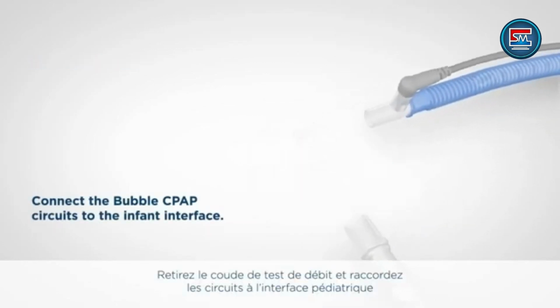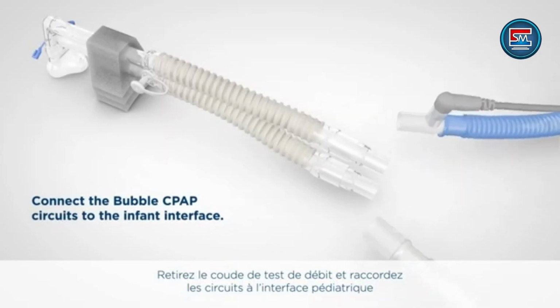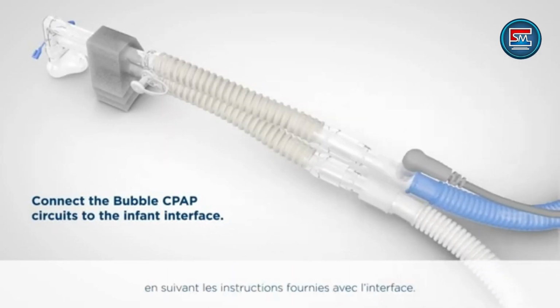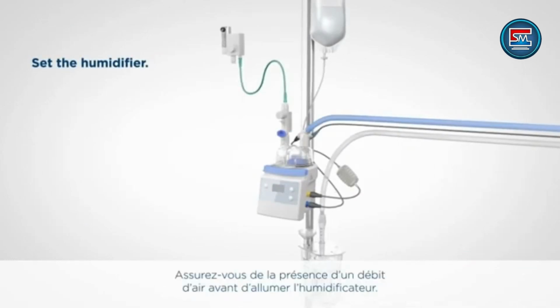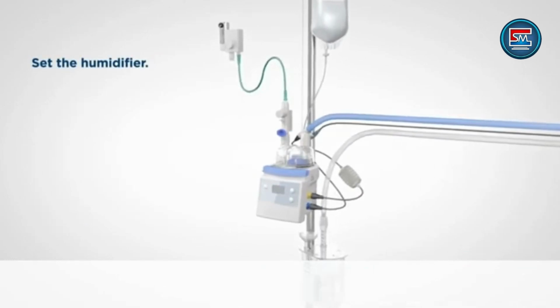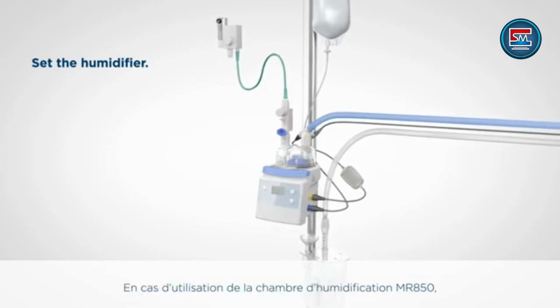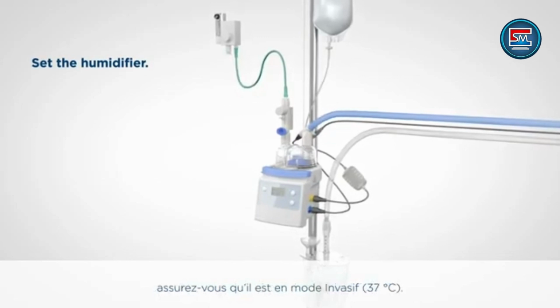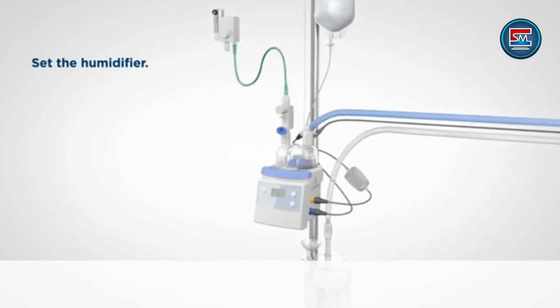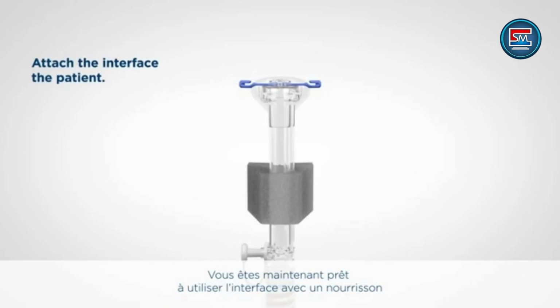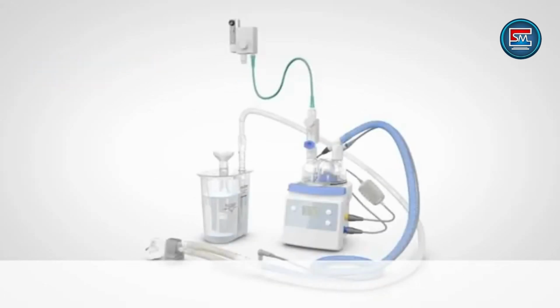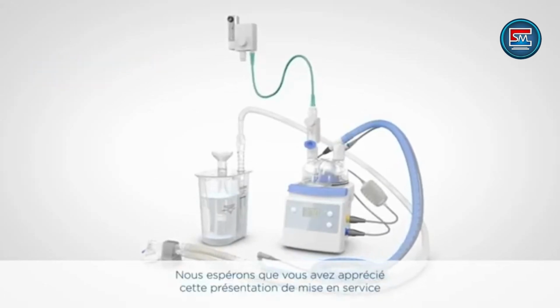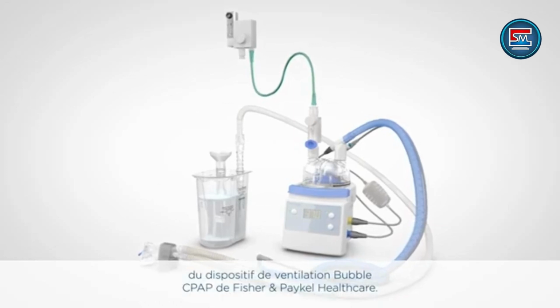Remove the flow test elbow and connect the circuits to the infant interface using the instructions provided with the interface. Ensure there is airflow present before turning on the humidifier. Turn on the humidifier. If using the MR850, ensure it is on invasive mode, 37 degrees Celsius. Now you're ready to connect the interface to the infant using the instructions provided with the interface. Ensure that the system is running before connecting to the infant. We hope you've enjoyed this in-service presentation on the Fisher & Paykel Healthcare Bubble CPAP delivery system.